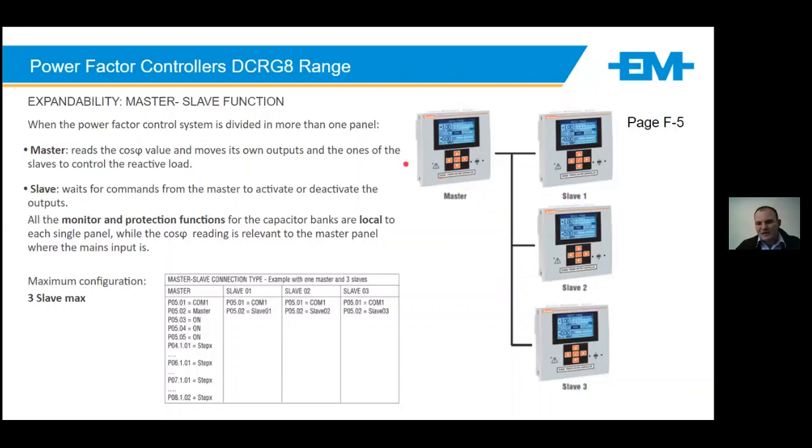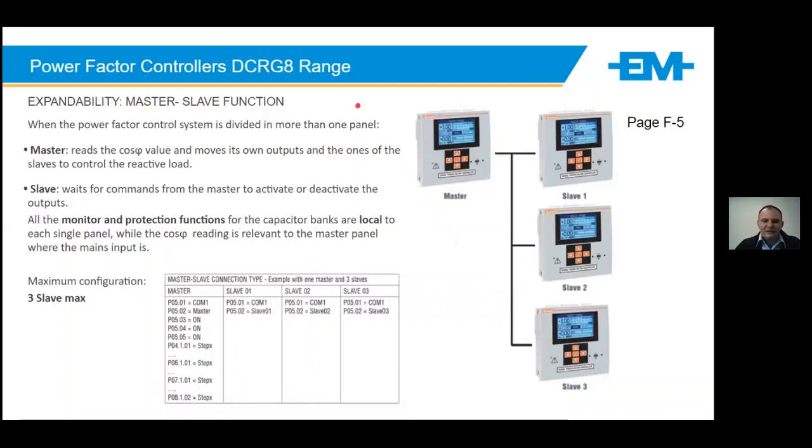When we hit the MVARs, basically we start looking at these sort of solutions, because it's not practical always to have all this control wiring between your panel. It's easier to have a system on one side, system on the other, comms bus between the two, and the master tells the slave what to do.